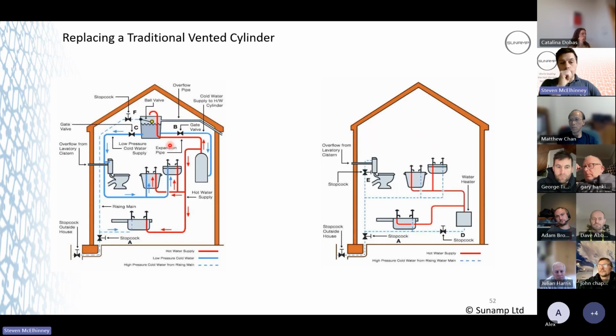again. And what was happening was the draw off for something had to go all the way up to the top and then back down into the kitchen. So it's a massive loop, and the customer was complaining about the time it was taking to heat and also capacity. If you've got a big leg of pipe there, that's energy from the battery sitting in the pipework, not getting used. So you want to try and make that more direct, don't you? Which is another important point.